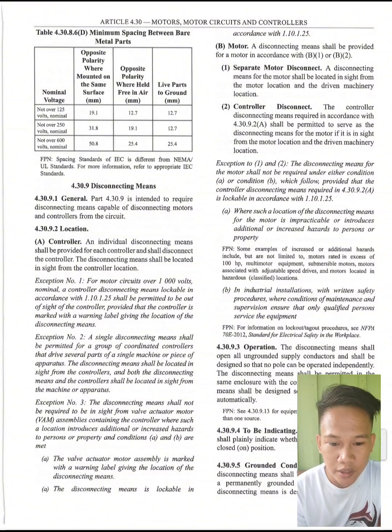So not over 600 volts nominal, 50.8, 25.4 for opposite polarity where held free in air, 25.4 for live parts to ground. So, we have here the 4.30.9 disconnecting means.